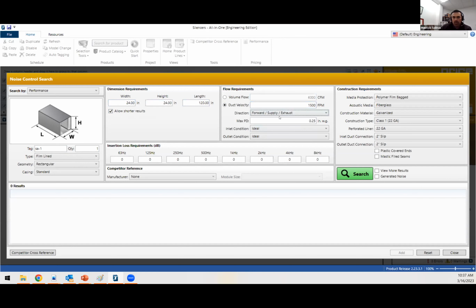Now, the good thing about all-in-one too is that you could add system effects. So the forward flow is typically referred to as the supply or exhaust. That means that the sound is traveling in the same direction as airflow. Or you do a reverse flow, which means for a return application, sound is traveling opposite to airflow. That changes performance, so you have to pay attention to that. Now, typically, I would say if you don't have a lot of information, hopefully you do, you don't want to select a silencer that's over 1/3 of an inch just to be safe. And then you can add system effects for pressure drop.